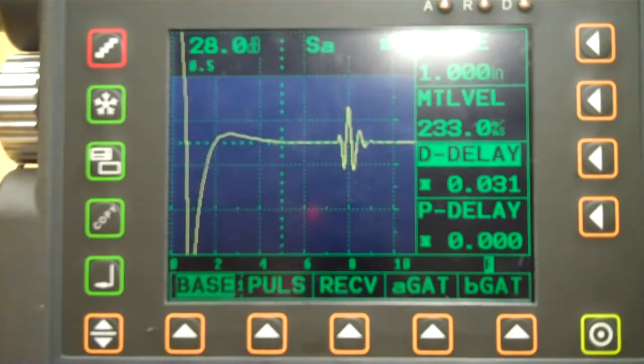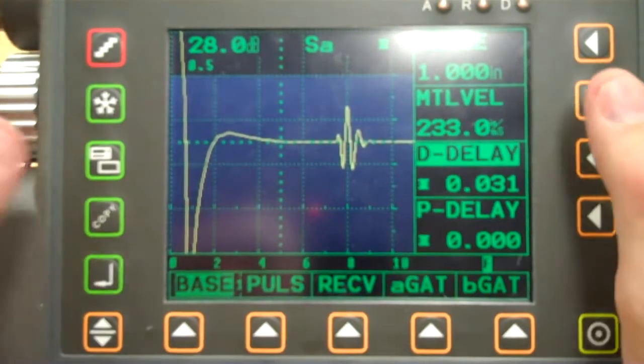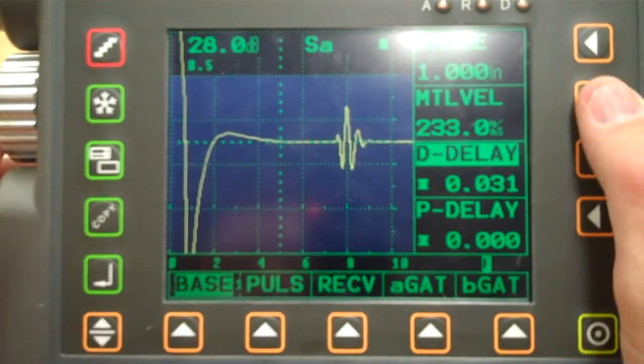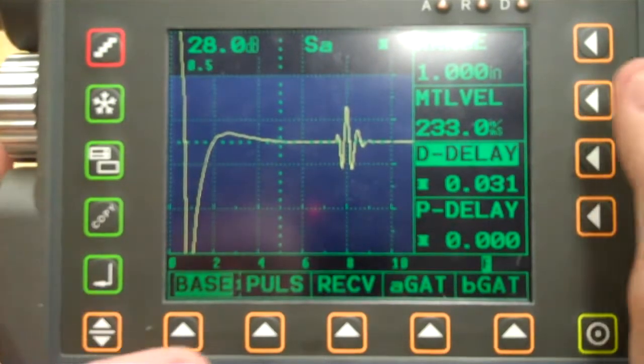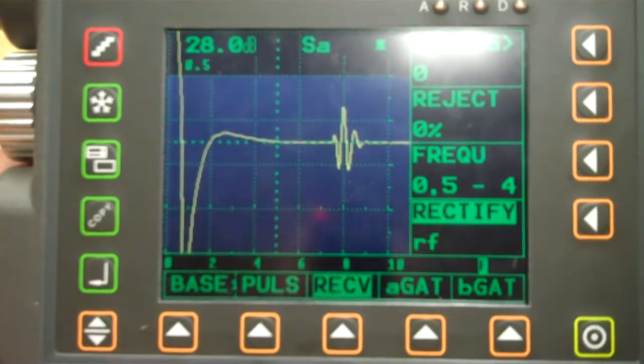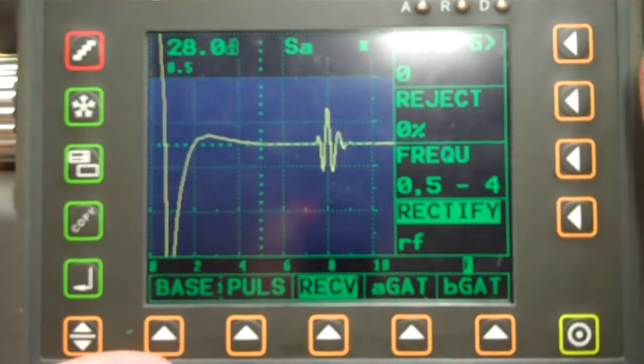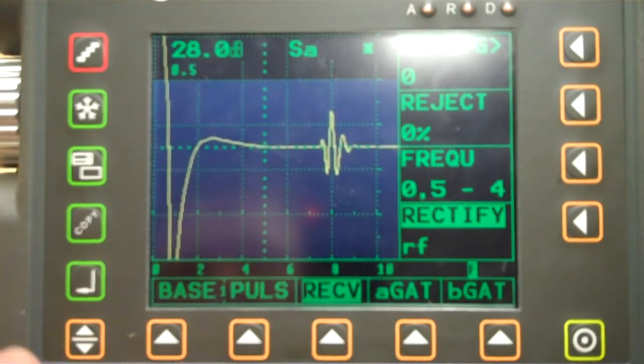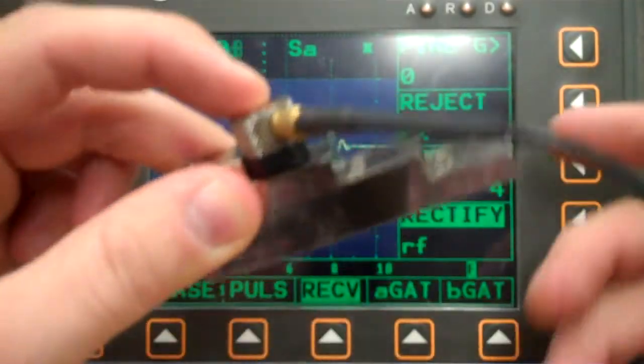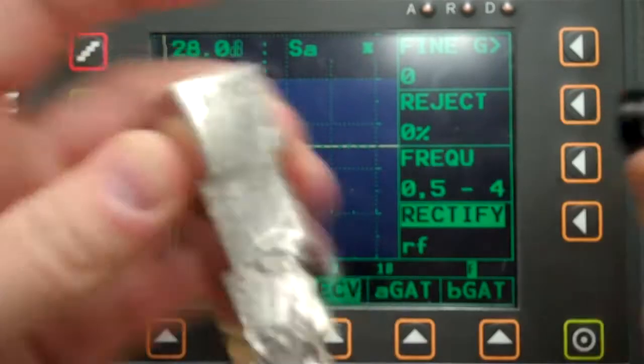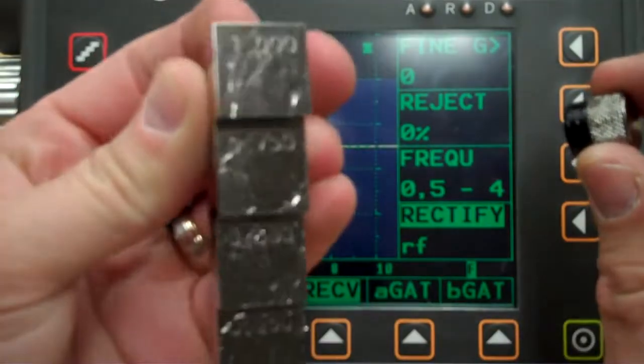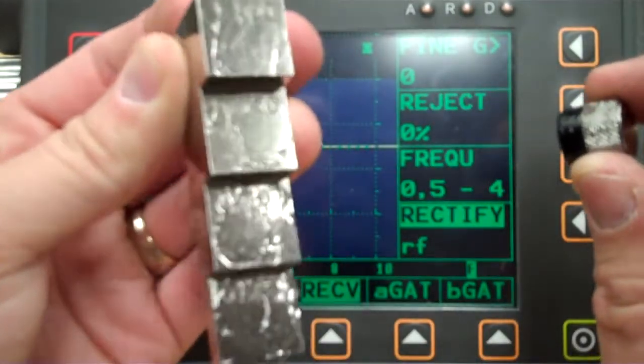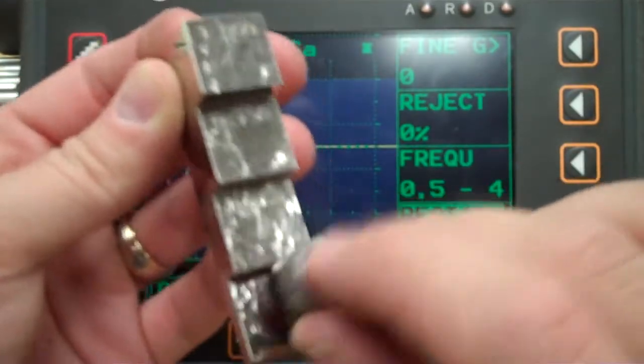So, first off here, just wanted to go back through the scope, kind of take a look at some of this stuff. We are right now looking at an RF signal. Okay, so let's go figure out what that is. Which you already know, there's 4 types of ultrasonic signals, and just so you can see where we're at, I just have my transducer on a 3/4 inch step of a 1 inch step wedge here. So there's 1 inch. You can read it there. It says 0.750, 0.500, 0.250 down here. 250, 5, 750, 1 inch.